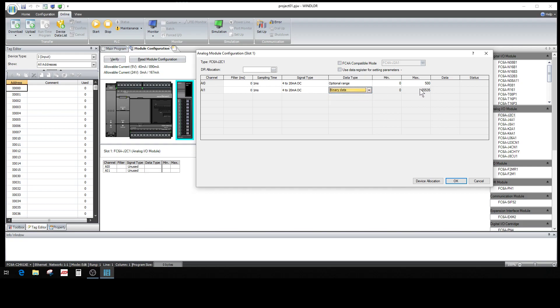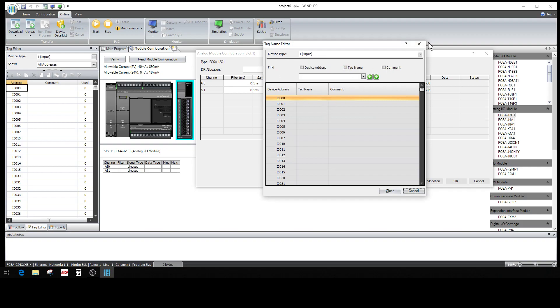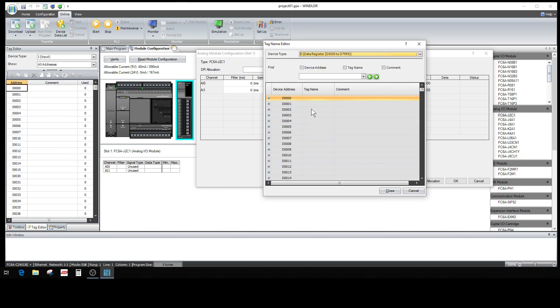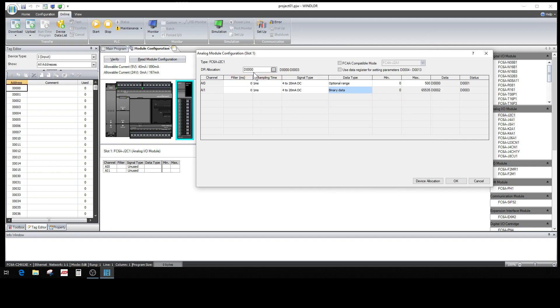Your data register is where it's going to actually send and hold the information from the field device coming back — it holds it in a data register in the PLC. You tell it where you want it stored right here. Click on that box, go to a data register, and pick one you have open. So now we have data register zero — it automatically assigns zero and one for this one, two and three for the next one. It's showing one and three but you're actually getting data zero, one, two, and three.